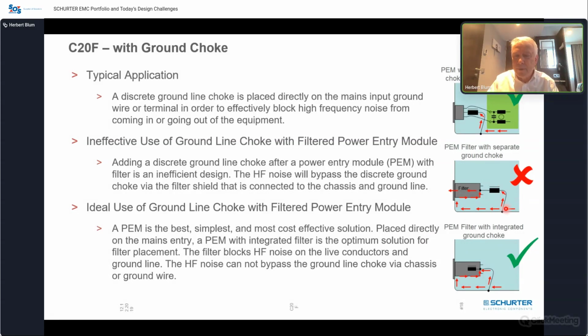You can also have, for example, an inlet filter here and an additional ground choke on the ground conductor on the back. The problem is this will not work, because the ground high frequency current will bypass this choke. It is blocked here, but it is everywhere, for example on the metal chassis or housing of the device, and this is connected to the filter housing. So it can easily bypass this ground choke. Integrate the ground choke - this is what works.